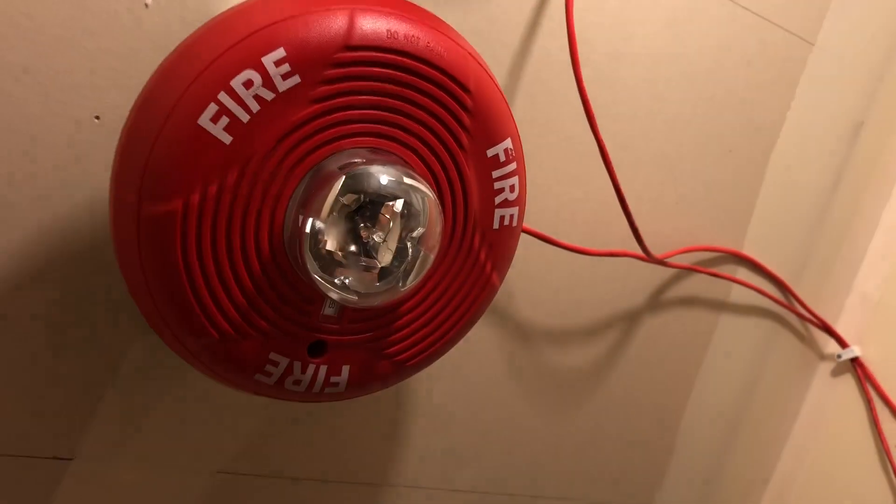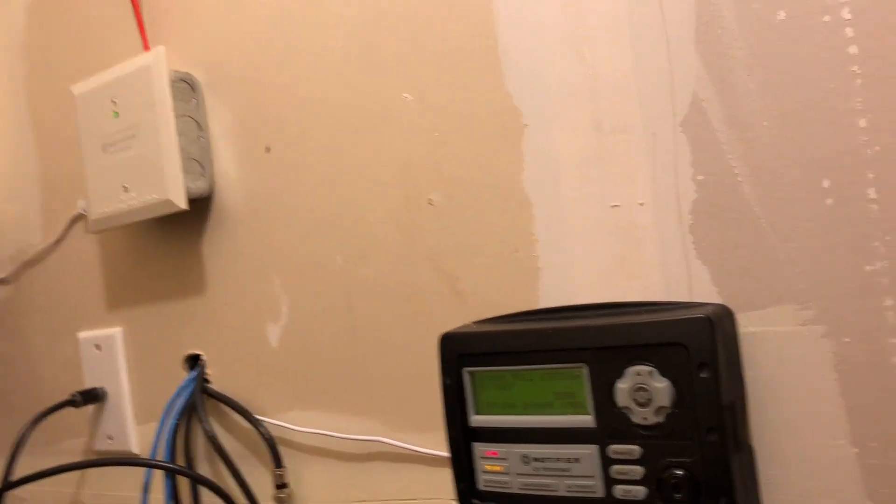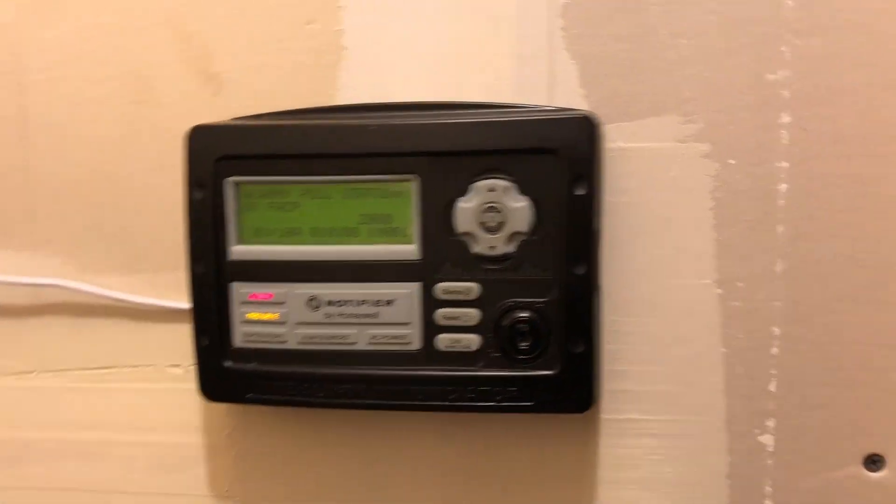Let's see if you can hear something over here. The problem — I wanted these to be doing temporal and they don't. The strobes won't even flash. So that's an issue. We'll silence that. That's quite loud and quite irritating, but it is our second stage.